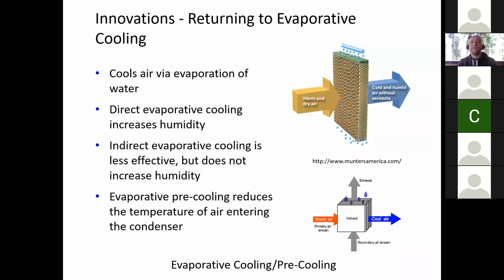Evaporative cooling works especially well in drier climates. There are two methods: we can add moisture directly to the airstream, which directly cools the air sensibly, or if we're concerned about the air getting too moist or wet, we can use what's called an indirect evaporative cooler, which has two airstreams.